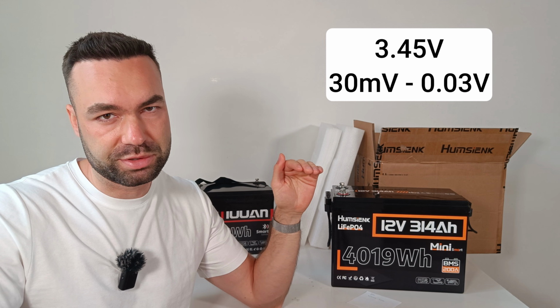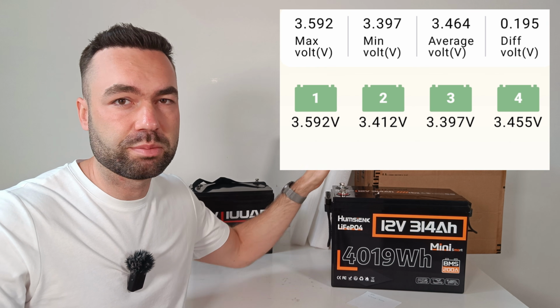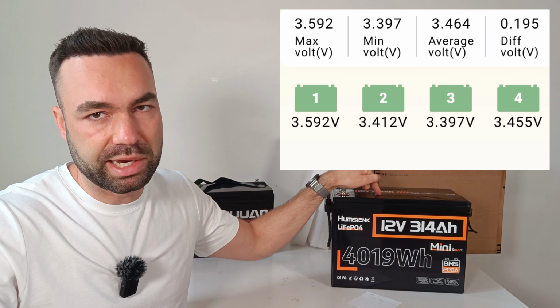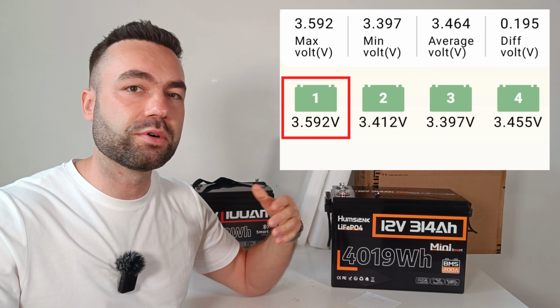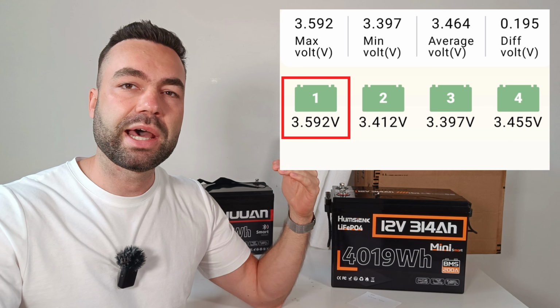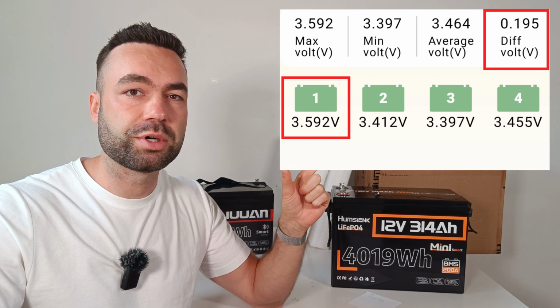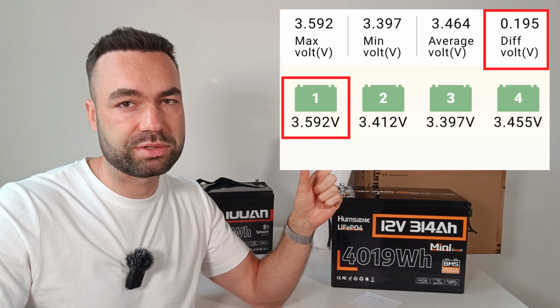The BMS is supposed to start balancing when the cell voltage goes above 3.45 volts and the difference between the cells is greater than 30 millivolts. That's normal behavior for a BMS, but this one wasn't balancing, even though the voltage was high enough and I was seeing a difference of 200 millivolts between the cells.